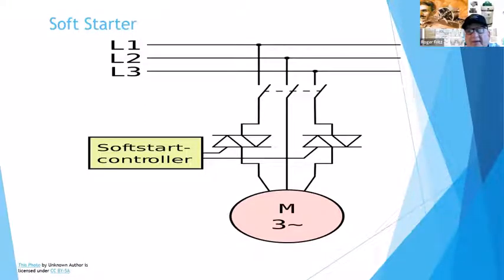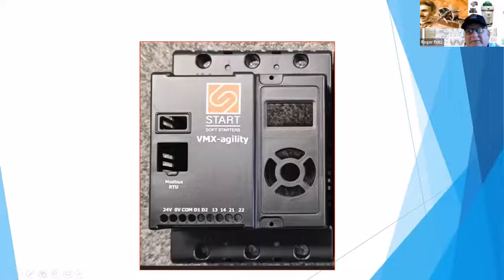And so from that, they went to the soft start devices. They were very simple, and they're still available. You've got your 3 legs in, your 3 legs out. Then you just have a simple control circuit here where you can turn it on or off, or that also gives different stages of acceleration as you want to soft start a motor. And these have become very, very good in the pumping industry, limiting water hammer, controlled start, controlled stop. Also, on the stopping, you're able to regulate that sine wave down. So you're also able to slow the motor and almost create a braking effect, to get rid of some of that mechanical energy.